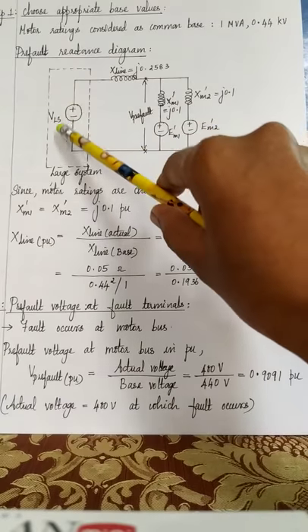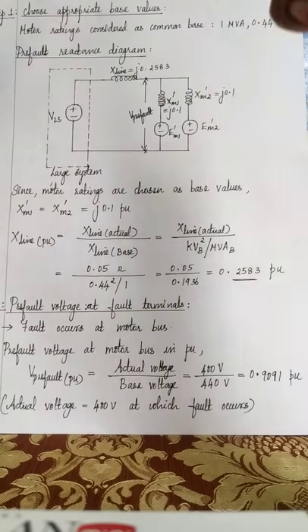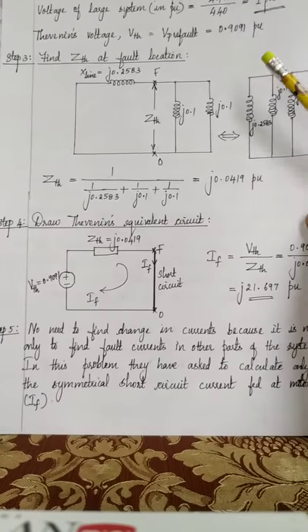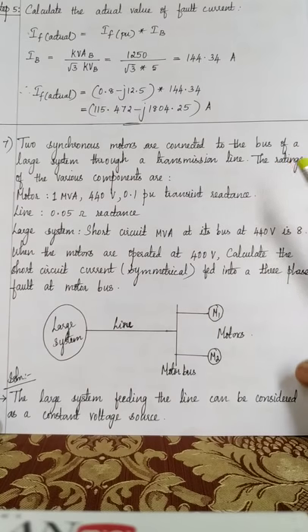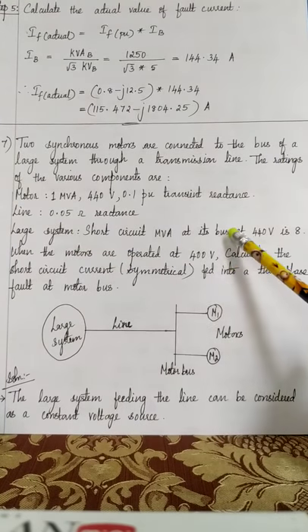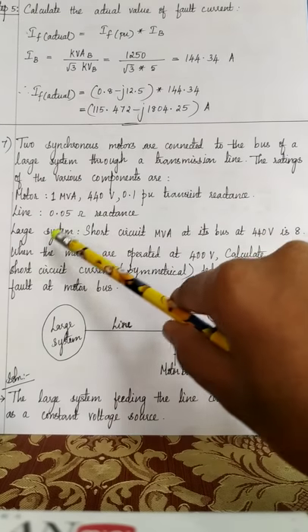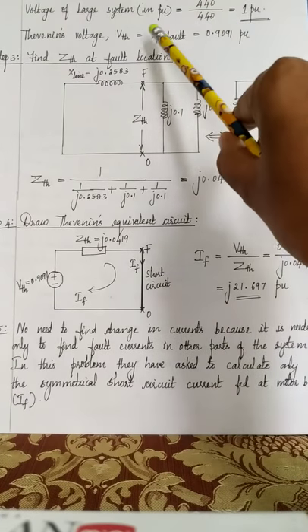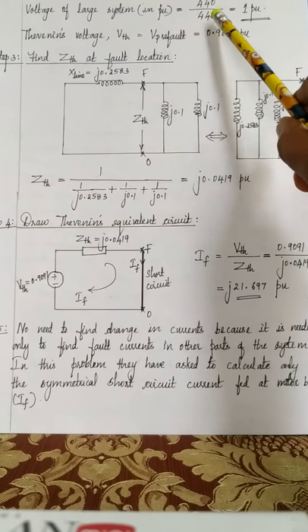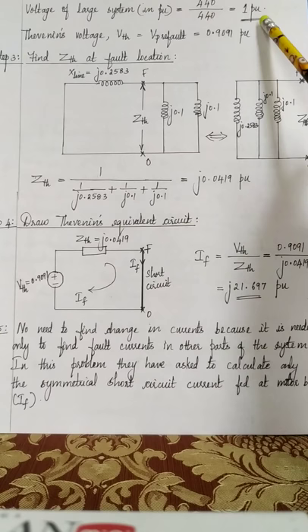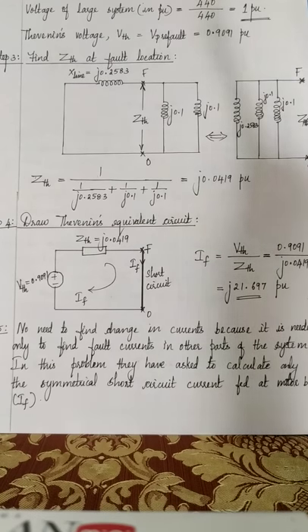Now we have to find VLS, the voltage of the large system in per unit. The large system voltage is given as 440 volt. So the actual value of the large system voltage is 440 volt. What is the base value? The motor rating, which is 440. So we get the voltage of the large system as 440 by 440, which is equal to 1 per unit. These two steps, the calculation of the prefault voltage as well as the voltage of the large system, are slightly different compared to the other problem. Instead of a generator, we have a large system, and its MVA rating and kV are given.